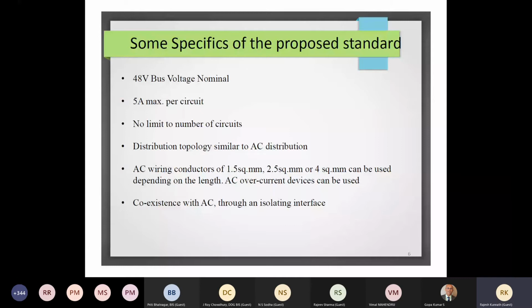also looks at things like what should be the size of the conductors that we are going to use. And here again, the intent was to use the wiring conductors that are used in AC, which is 1.5 square mm, 2.5 square mm, 4 square mm. The reason we would have multiple sizes is essentially because we want to ensure that the I square R losses are minimized. The voltage drop is also minimized from the start to the end of the distribution. There's also some inclusion of the coexistence with AC. That is, eventually when AC comes in, how are we going to connect those as well?